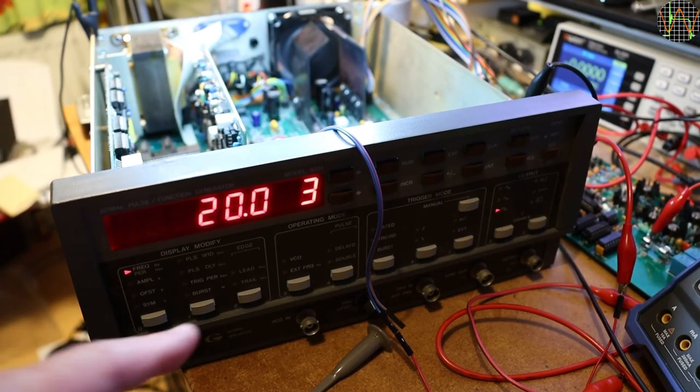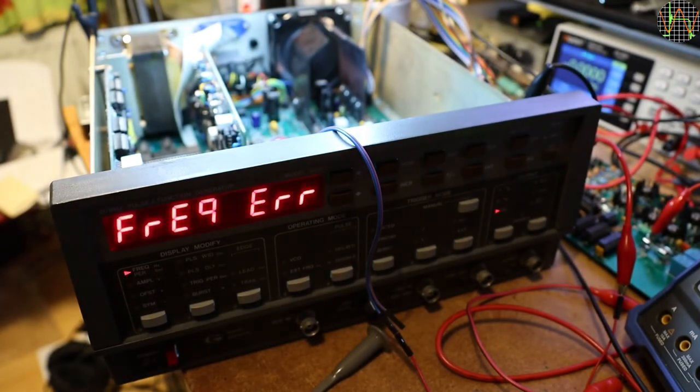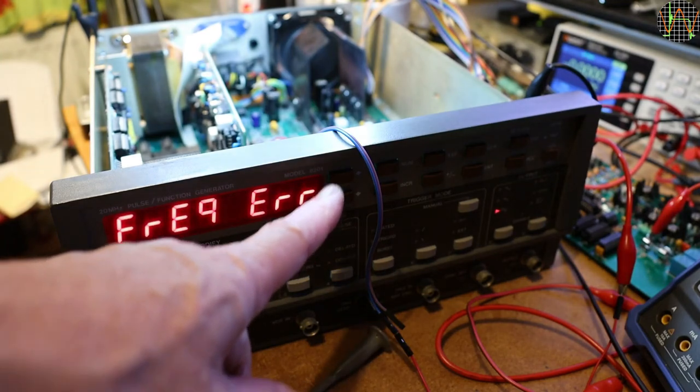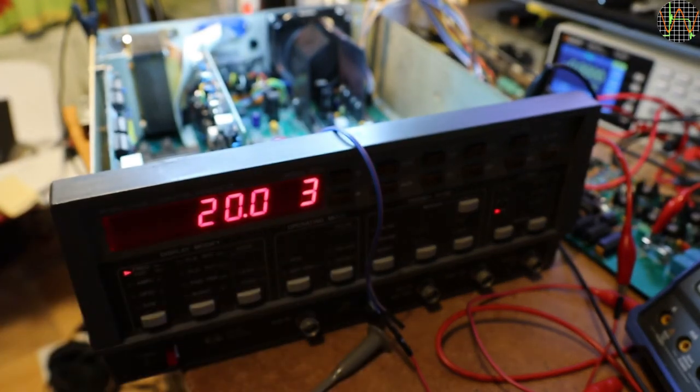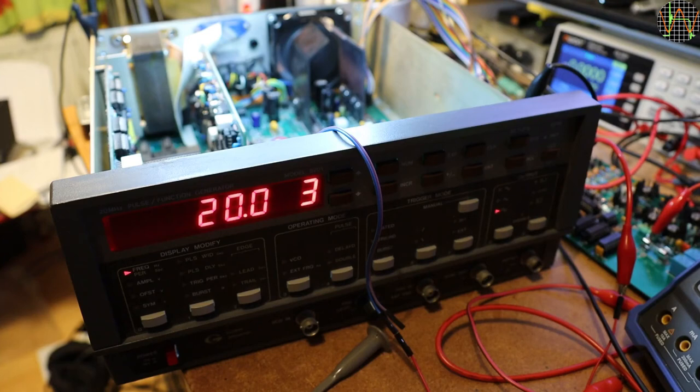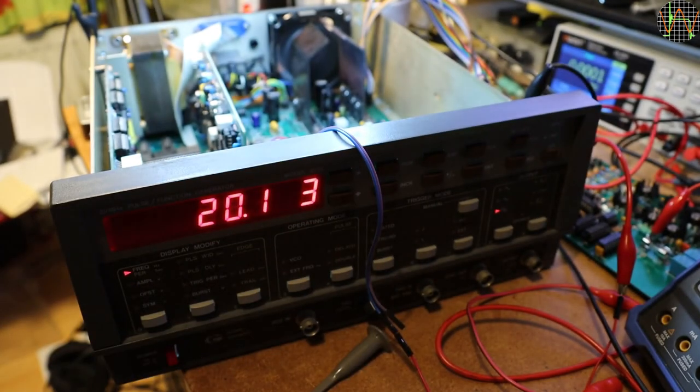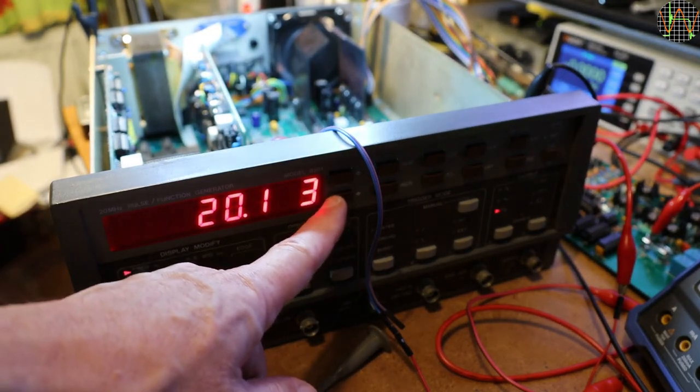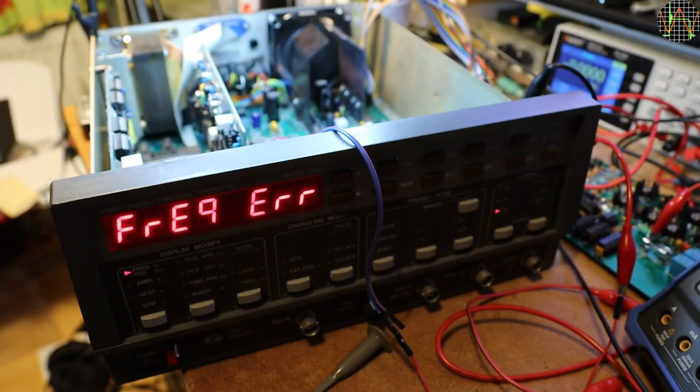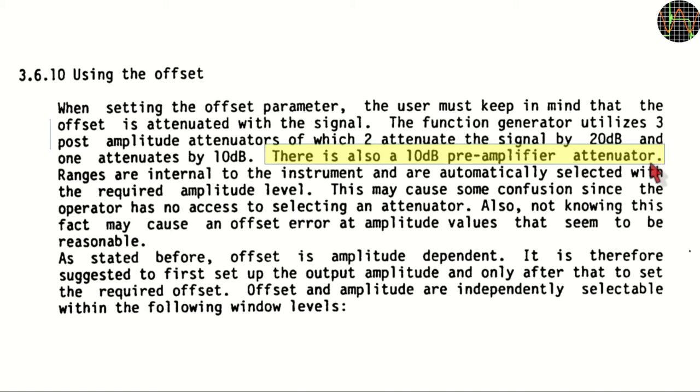And sure, there are more issues. For example, I can select 20kHz as frequency but not 19.99. It shows frequency error instead. So either I am making a silly mistake or there is something wrong at the very heart of the generator. To rule out operator errors, I decided to spend time to actually read the manual from beginning to end. To my amazement, I found this sentence tucked away in a section discussing the use of the offset function. So there is actually another 10dB attenuator, but it is in the pre-amplifier instead at the output of the final amplifier as all the others. I did check and this fact is not mentioned anywhere else in the manual, in particular not in the section on attenuators.